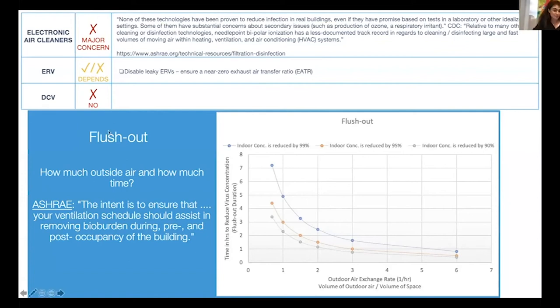The last here is flush out. Flush out refers to how much outside air and how much time. Flush out doesn't mean 100% outside air and doesn't mean you have to open your building 2 hours before and 2 hours later. You can do a performance-based flush out. For ease of use, I made this graph and feel free to use it. On the y-axis is how much time I need to do flush out, how much time I should clean the air between events or between services or when people go home.